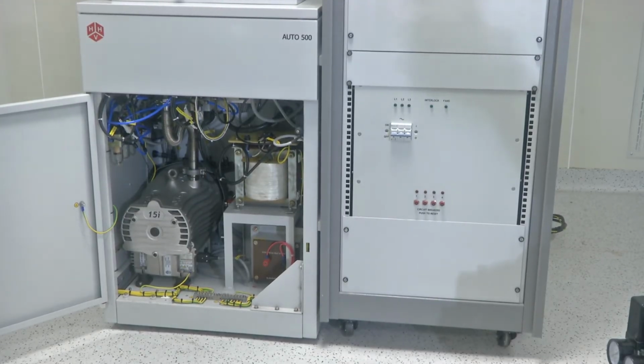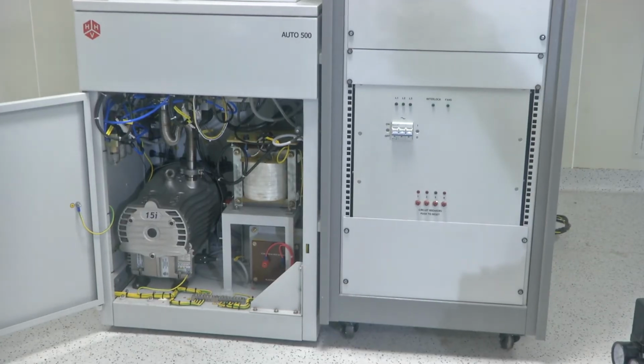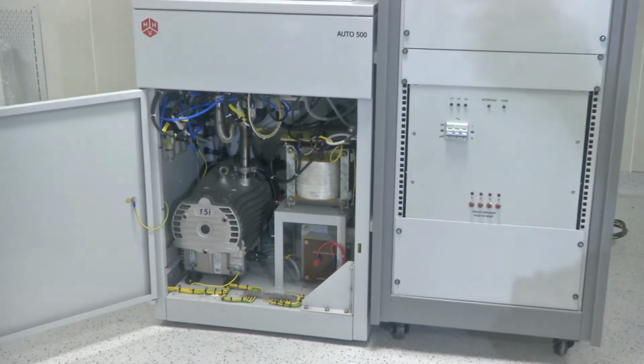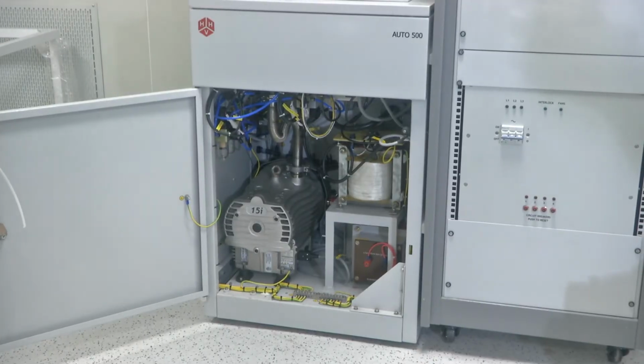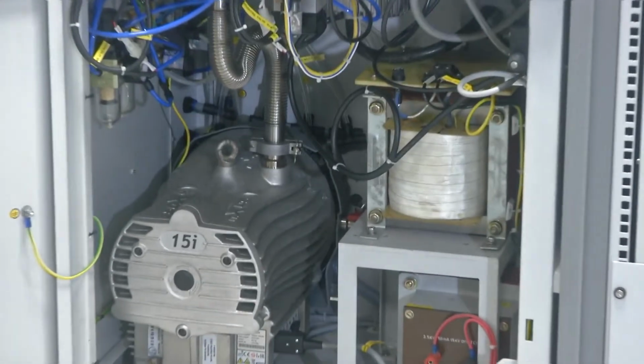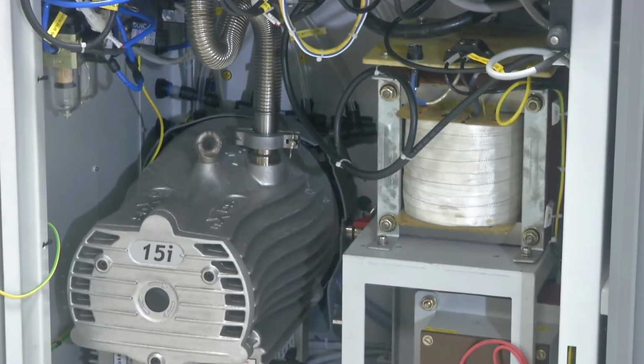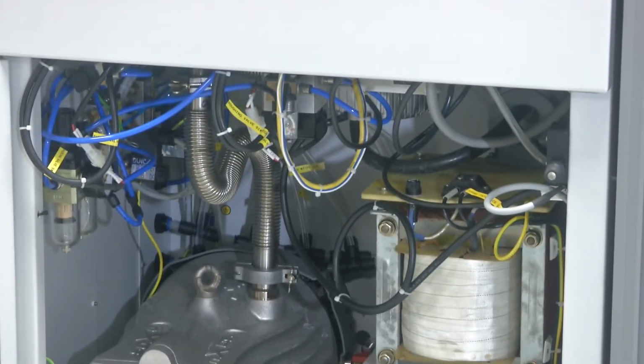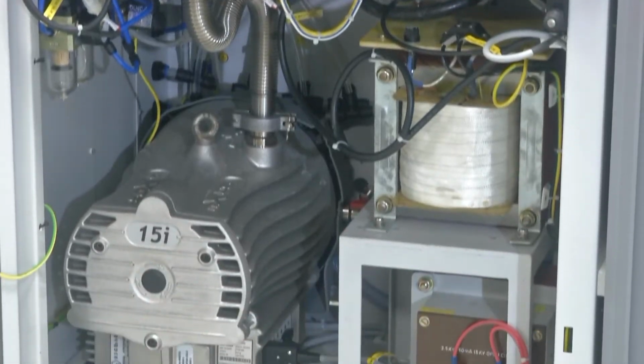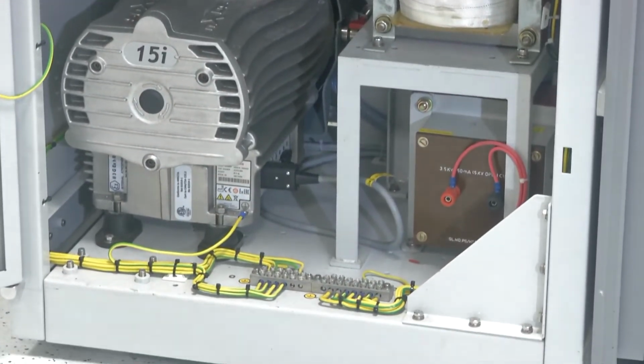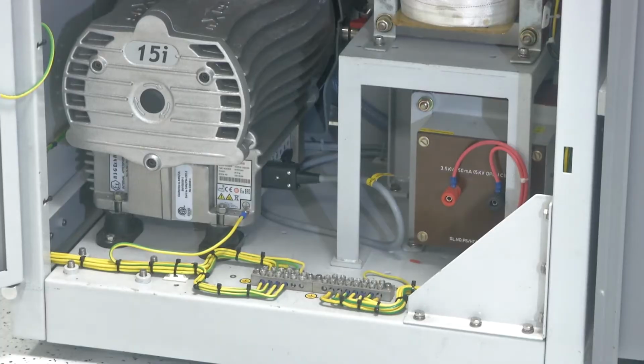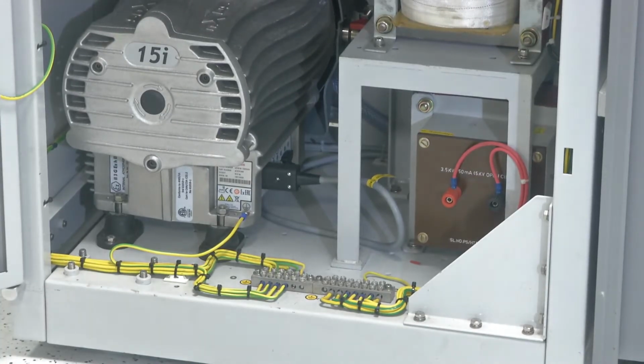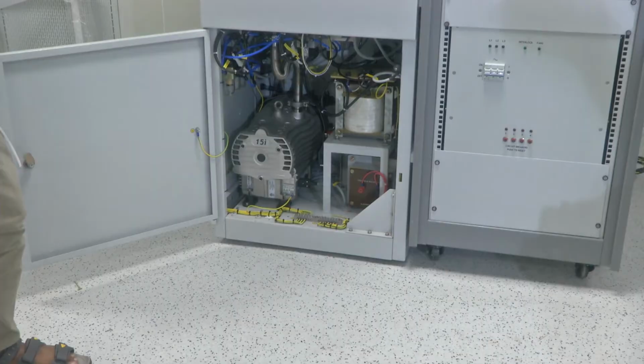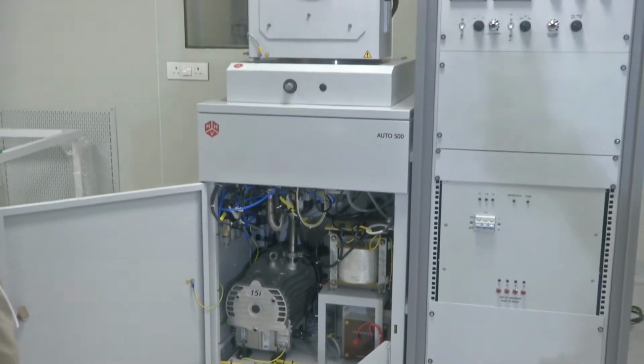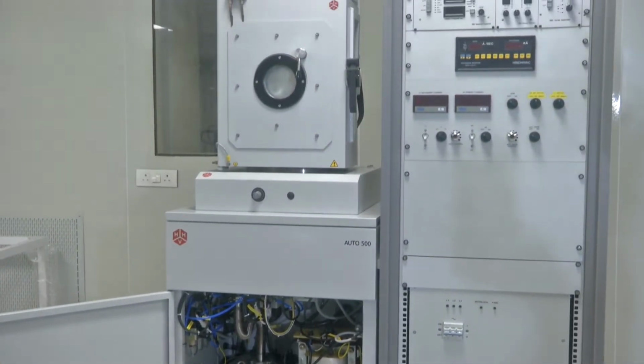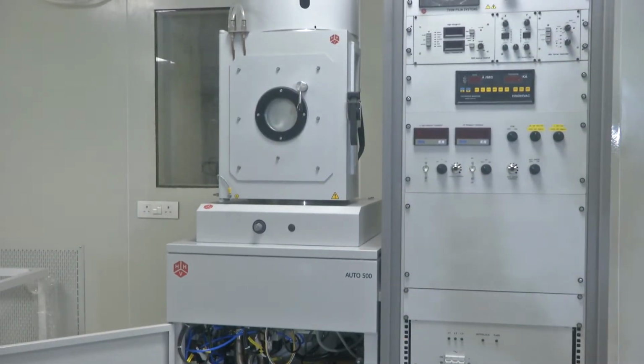Once the turbo molecular pump is switched on, wait 20 to 30 minutes until the turbo ready indication comes. After the ready indication comes, turn the combination valve to the roughing position. Before opening the high vacuum valve, your chamber should be at rough vacuum, minimum -2. Otherwise, it should not go directly from atmospheric condition. We have protection interlocks. If you try to switch on, it will not switch on.